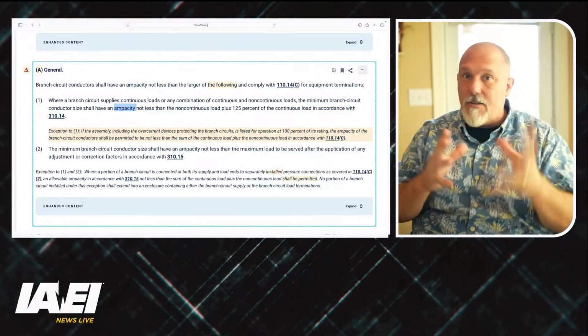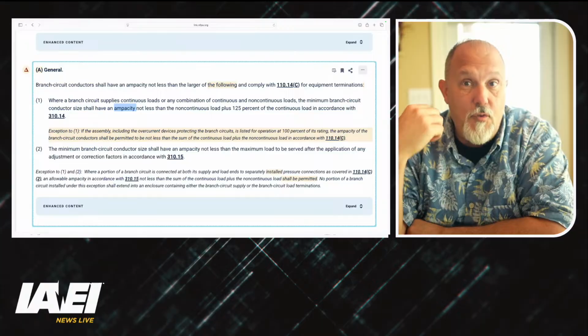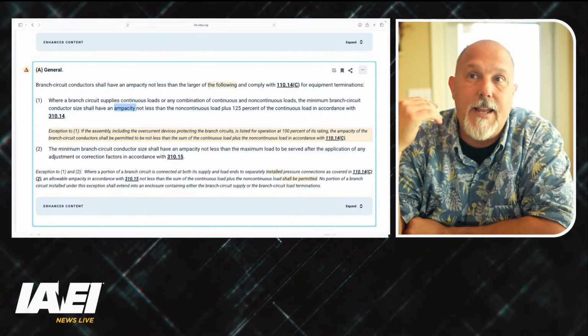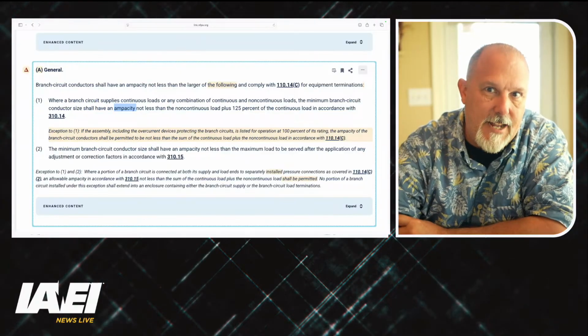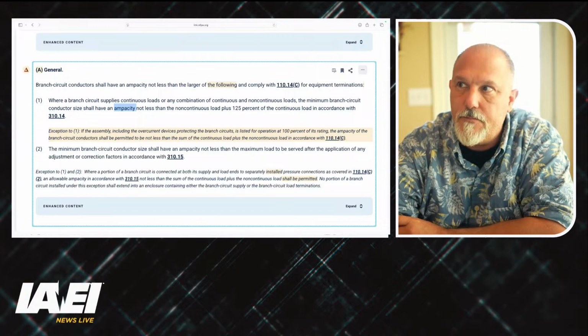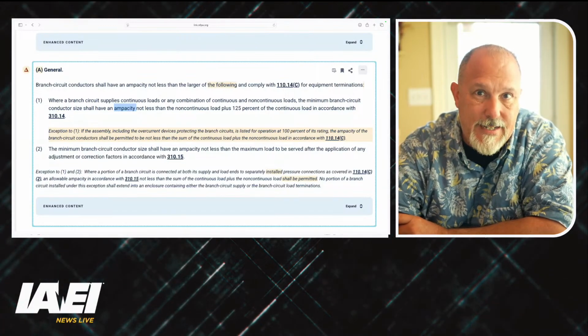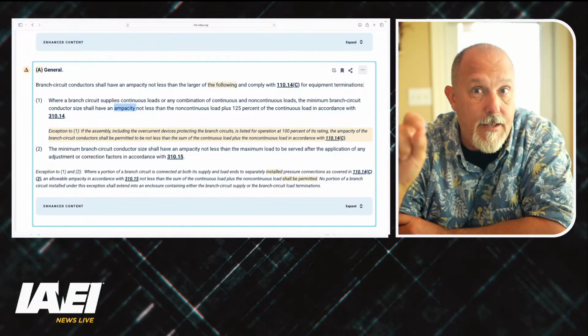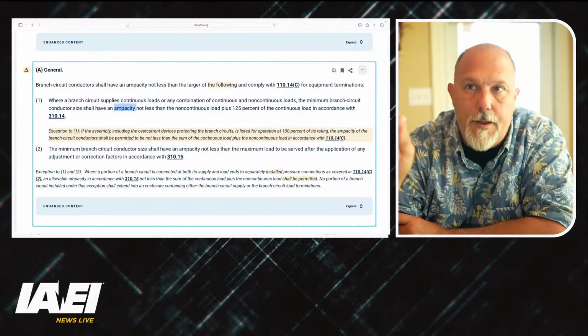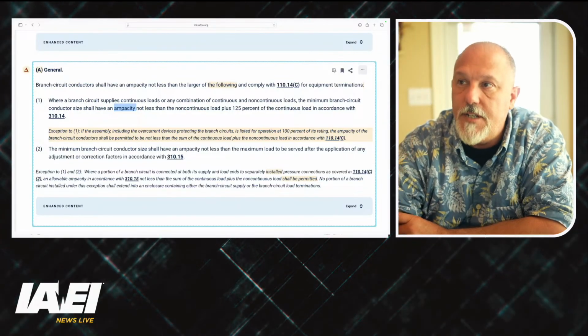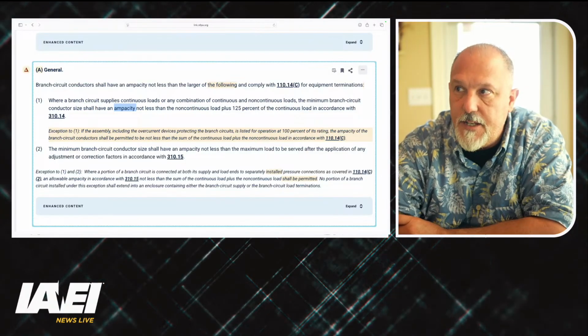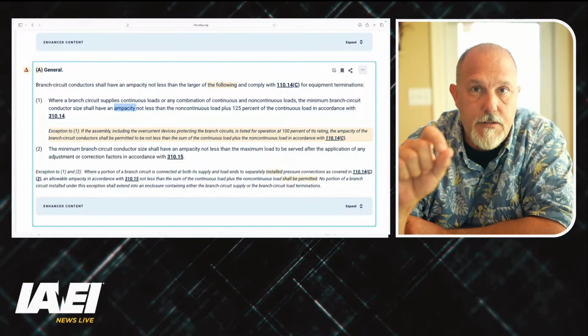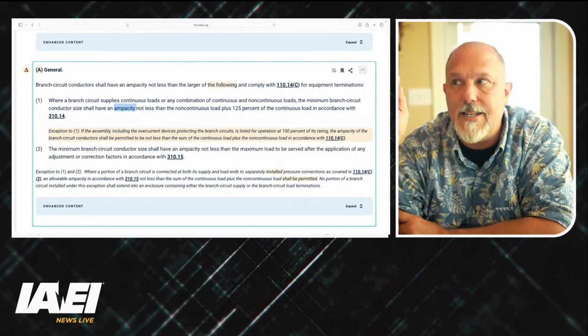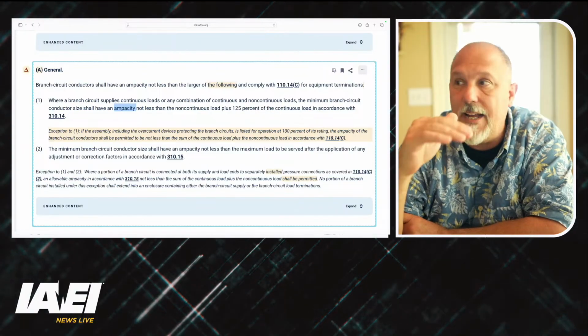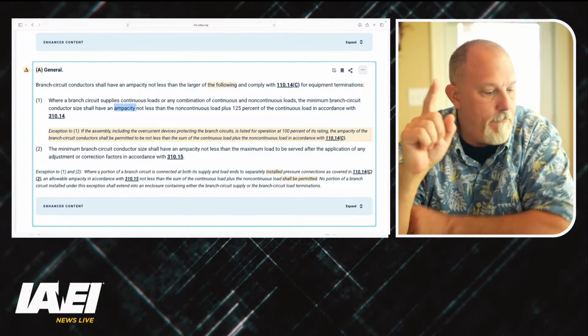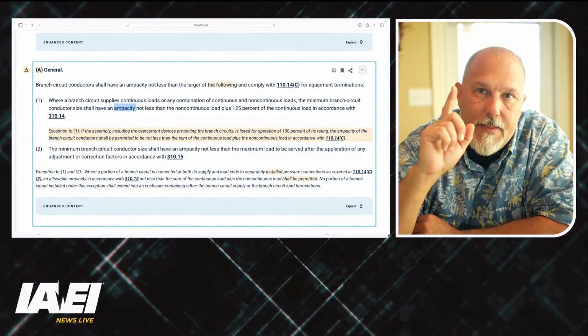But you'll notice in the parent text, which I couldn't understand before, now this is all coming together for me. You're probably sitting there saying, Tom, I've done it this way, and I don't know why it took you this long to figure this out. But I'm a slow learner. So what 110.14(C) means in the parent text of A, and where you would use it, is in A1. What you do is you take 125% of the continuous plus the non-continuous, and then you go to Table 310.16 and select a conductor there based upon the equipment temperature rating.